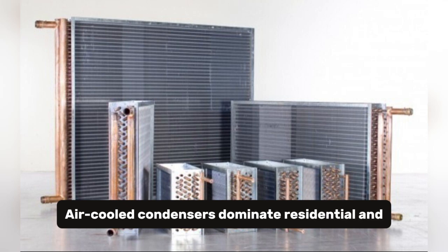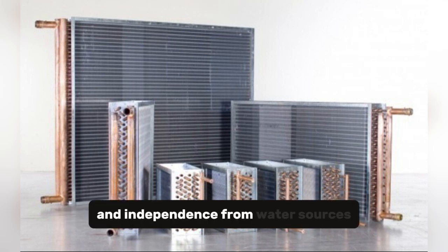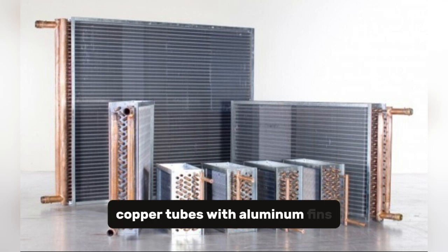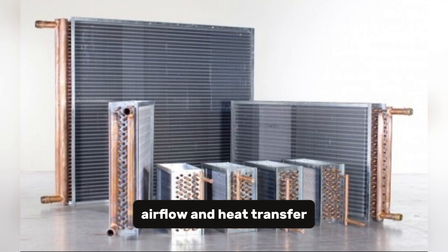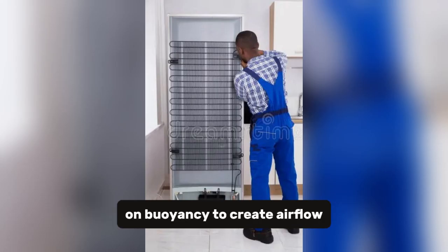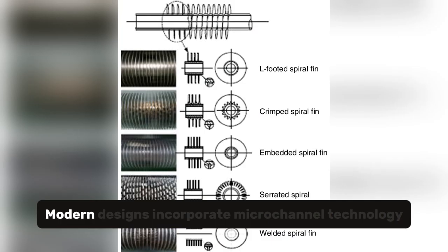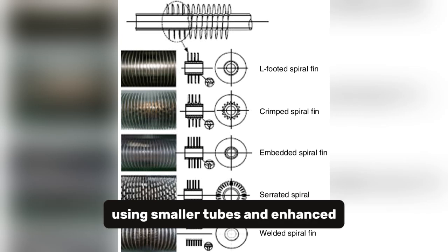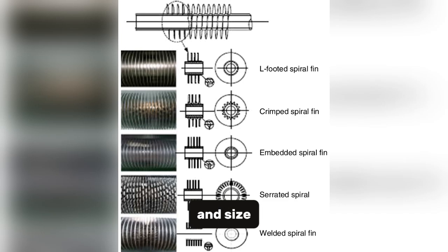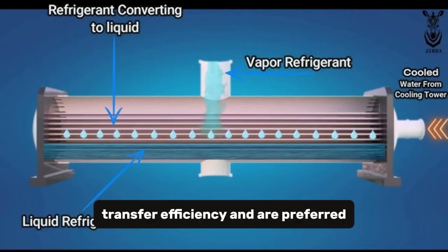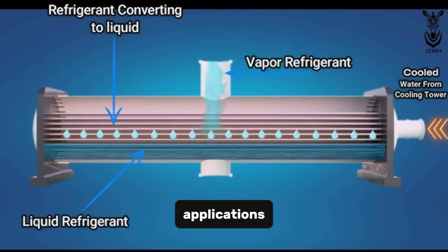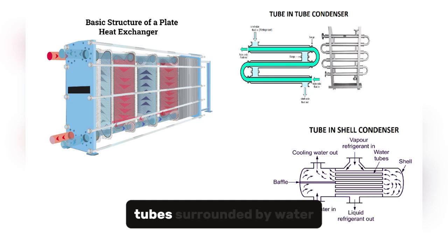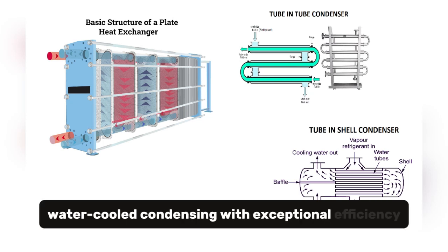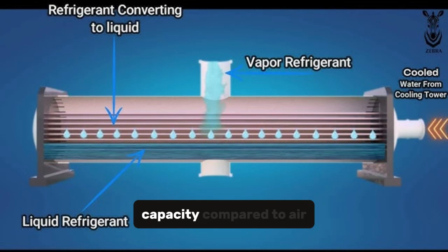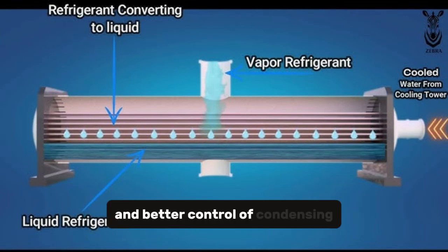Air-cooled condensers dominate residential and small commercial applications due to their simplicity and independence from water sources. The most common type uses copper tubes with aluminum fins, arranged in configurations that optimize airflow and heat transfer. Natural draft air-cooled condensers rely on buoyancy to create airflow, while forced draft units use fans to move air across the coils. Modern designs incorporate microchannel technology, using smaller tubes and enhanced fin geometries to maximize heat transfer while minimizing refrigerant charge and size. Water-cooled condensers offer superior heat transfer efficiency and are preferred for large commercial and industrial applications. Tube condensers use refrigerant flowing through tubes surrounded by water, while tube-in-tube designs work well for smaller applications. Plate heat exchangers provide compact water-cooled condensing with exceptional efficiency. The key advantage of water cooling is water's superior heat capacity compared to air, allowing for more compact condensers and better control of condensing temperature.